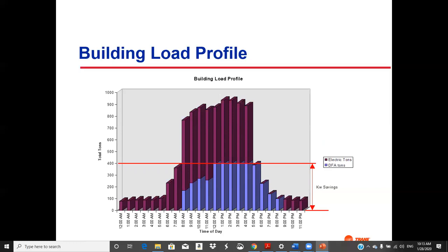Say we're splitting the load. 400 tons is the absorber. It can come up to that, and they're only bringing it up 1, 2, 3, 4, 5, and then the load was a little bit less. So basically 6 hours. This may be that on-peak period, and they're ramping the thing up to get it ready to go. But you can see during the peak portions of the day, 12, 1, 2, 3, 4, you're not quite at 1,000, but you've got 400 here, and you're loading the centrifugal pretty good. If you didn't have this absorber, you would have another 400-ton electric chiller so that you were able to condition the building. So you can see the bite out of the total load that they're showing the absorption chiller taking.